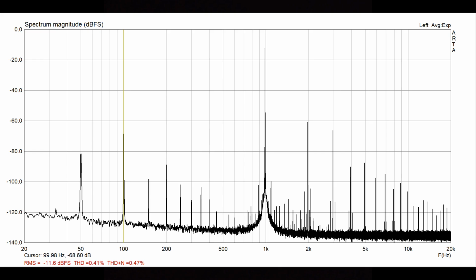Here is the single-ended output. The SPL is actually pretty good. As you can see here, total harmonic distortion is 0.41%, so that's really not bad at all. But we do see 50 Hertz and 100 Hertz, and we also see how mains frequency is kind of modulated and mixed together with the 1 kilohertz.